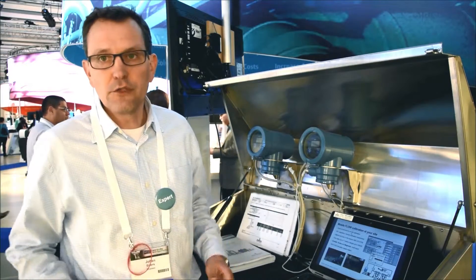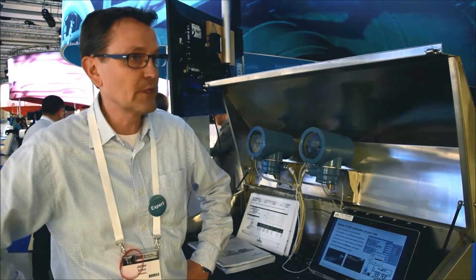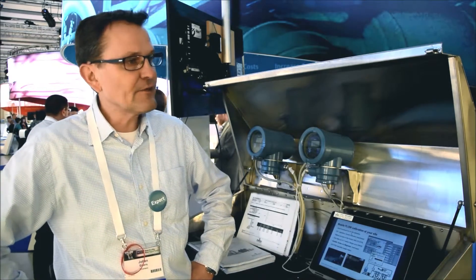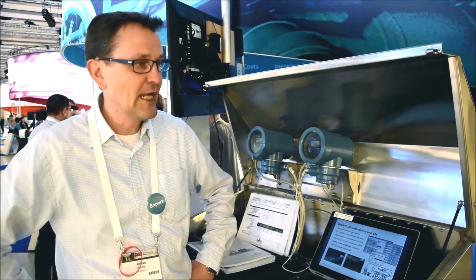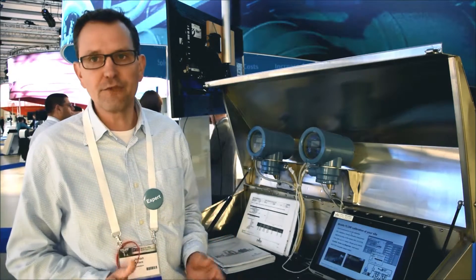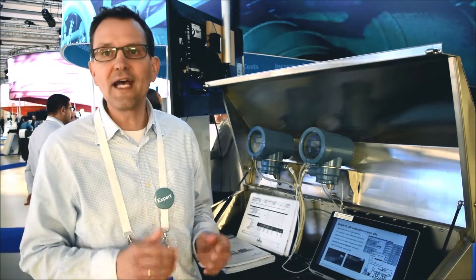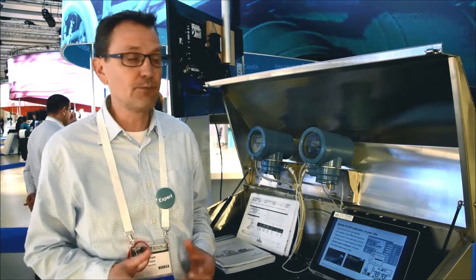As I already showed you, you can put your unit under test in the calibration rig, which we can place on-site. It is very easy to calibrate Coriolis meters, Vortex meters, and Mag meters up to 3 inch. Our calibration rig covers from 1.8 kilogram per minute up to 1600 kilogram per minute.